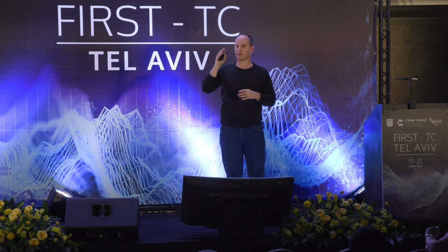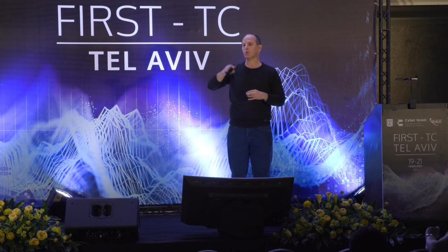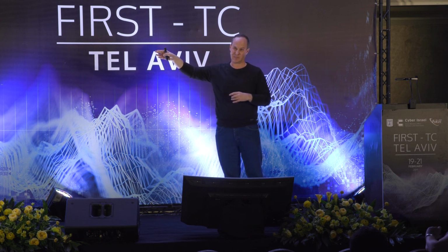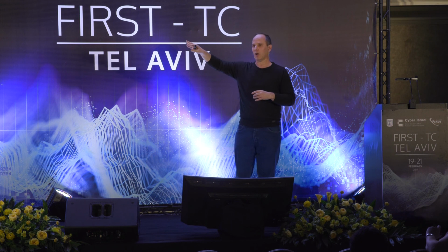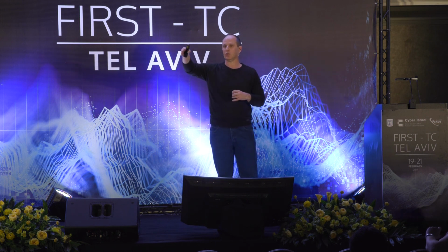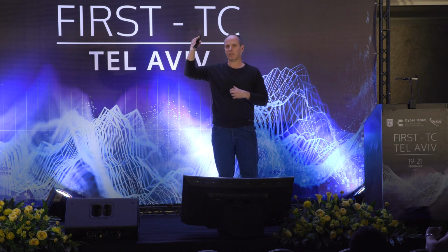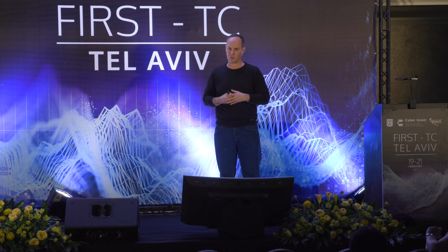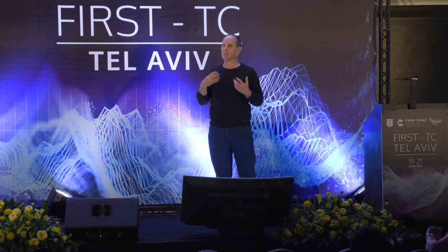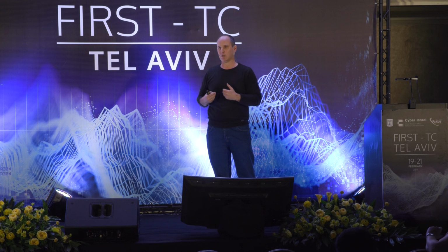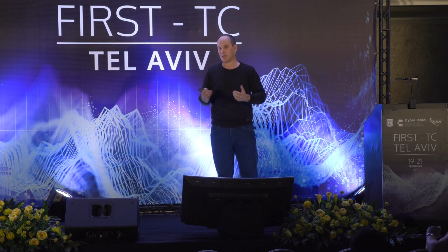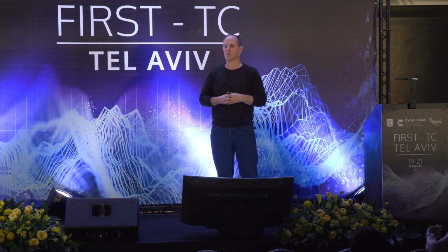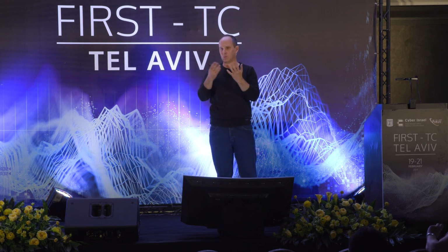But we're able to get some of the things that you mentioned with those facilities that chose also to implement those ICS IDS systems. So most, if not all, of those ICS IDS systems are capable of looking into anomalous Modbus traffic. Some have support for more advanced protocols. They raise flags, they generate alerts, generate incidents. I do get those alerts, and I'm using it basically to create an incident based on this information. So the short answer is that in our case, we're not doing it.